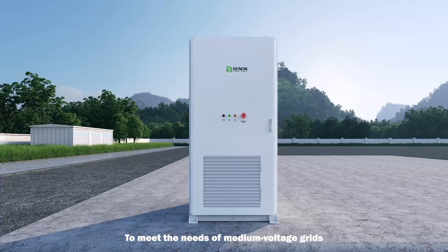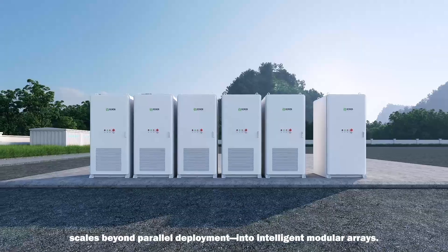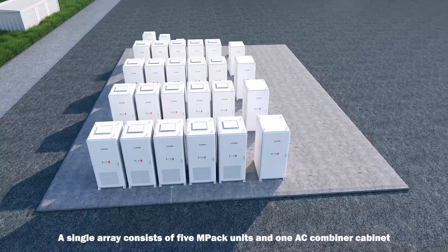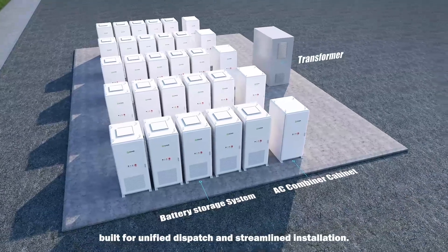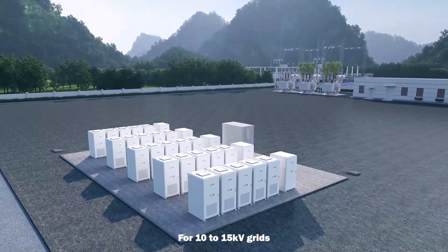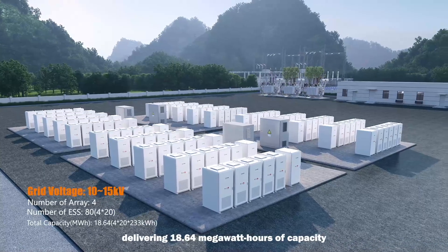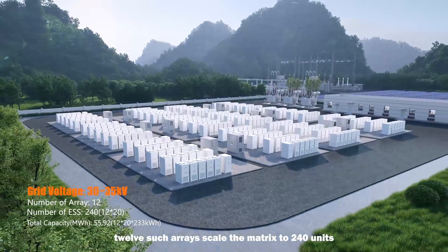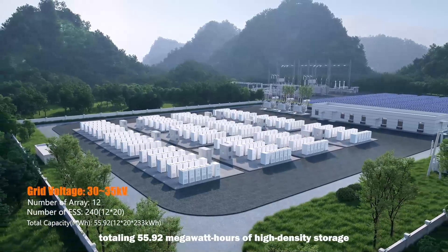To meet the needs of medium voltage grids, MPAC-233A scales beyond parallel deployment into intelligent modular arrays. A single array consists of five MPack units and one AC combiner cabinet, built for unified dispatch and streamlined installation. For 10 to 15 kV grids, four arrays form a matrix of 80 units, delivering 18.64 MWh of capacity. For 30 to 35 kV grids, 12 such arrays scale the matrix to 240 units, totaling 55.92 MWh of high-density storage.